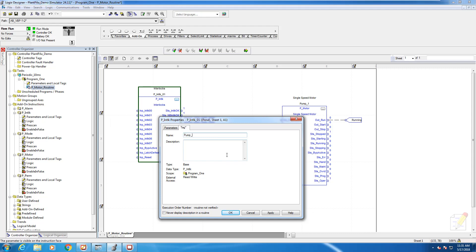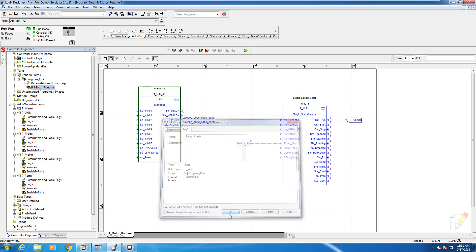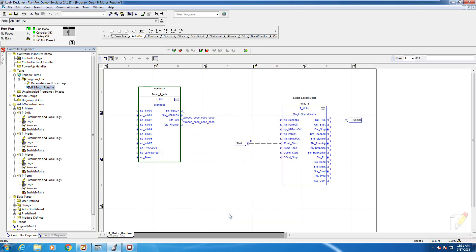For the motor block which we called pump one to recognize the interlock block, this tag name is critical. The way it works is you start with the tag name of the motor block, in our case pump one, underscore, followed by INTLK for interlock. By using that naming convention, we have the ability for the motor block faceplate to automatically navigate to the interlock faceplate.